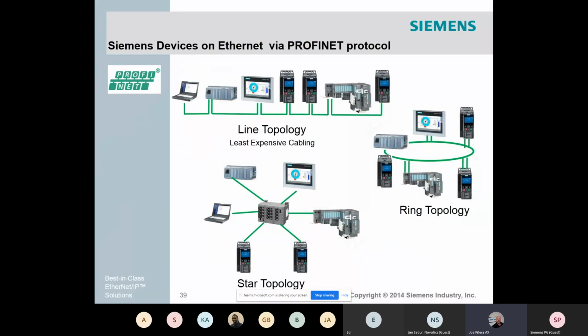A star topology guarantees that if one device goes down, like hit by a forklift or damaged in some way, everything else will continue to operate normally. It is simple, everybody can do it. It requires only 1 port per device. The drawback is that you are putting all your eggs in one basket and having to wire everything back to the main controller again.